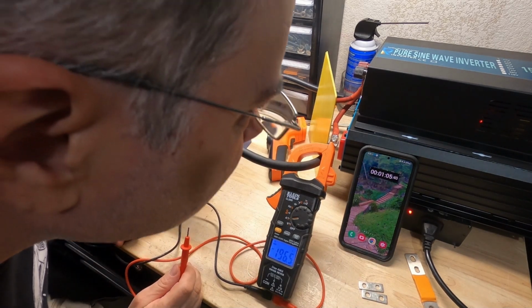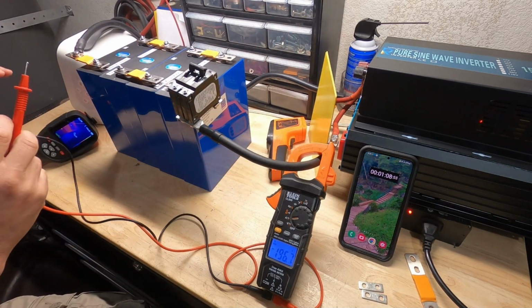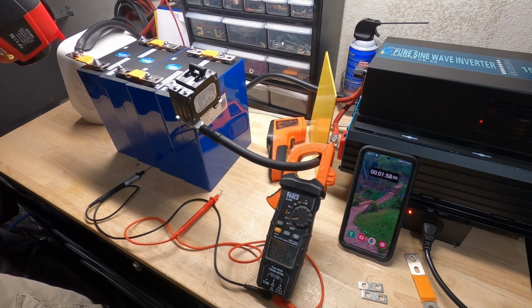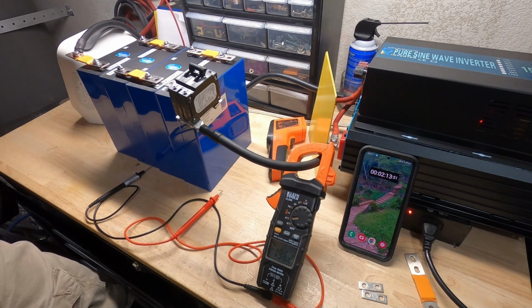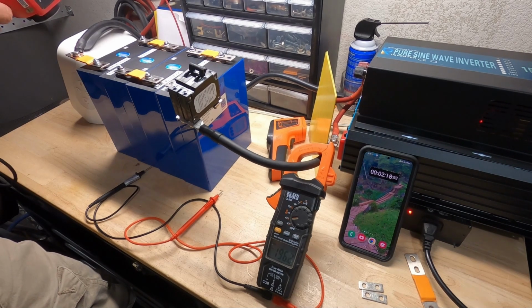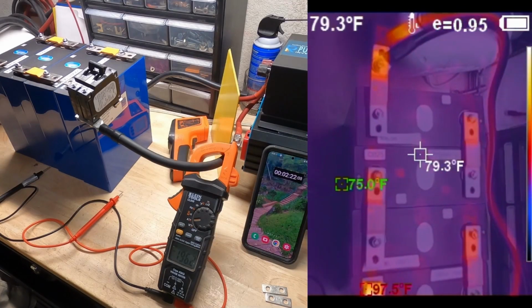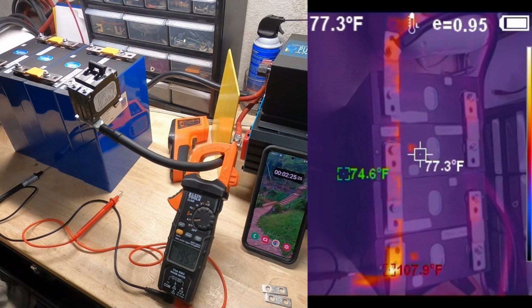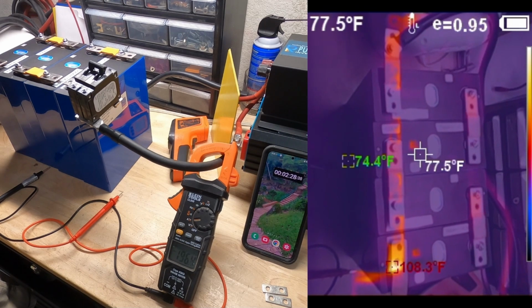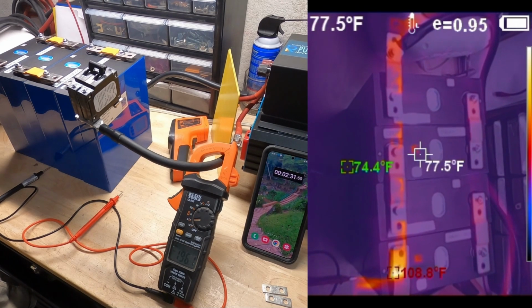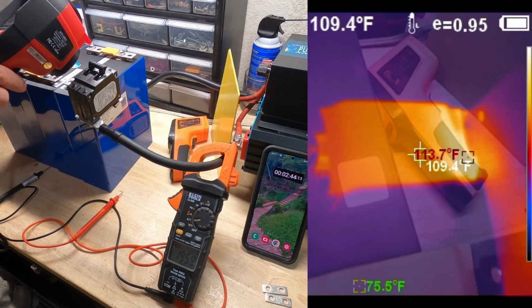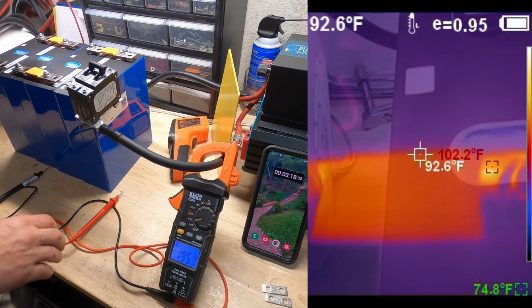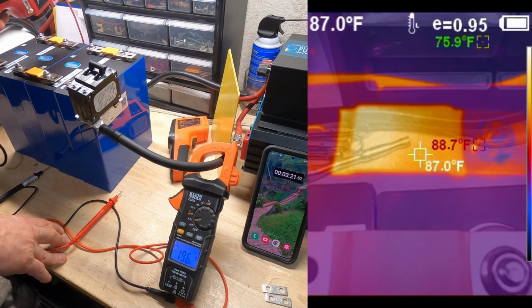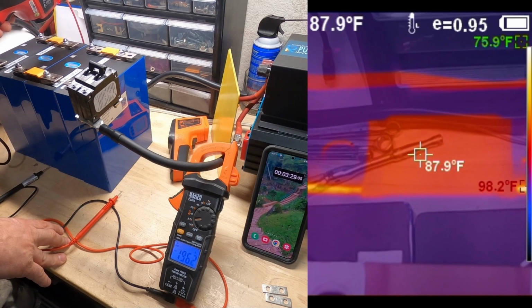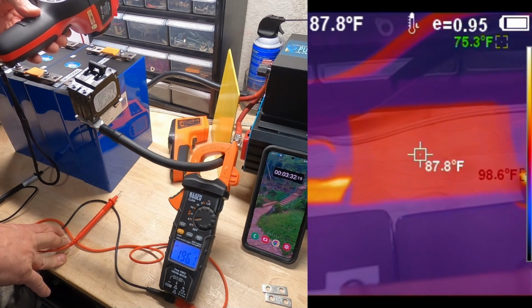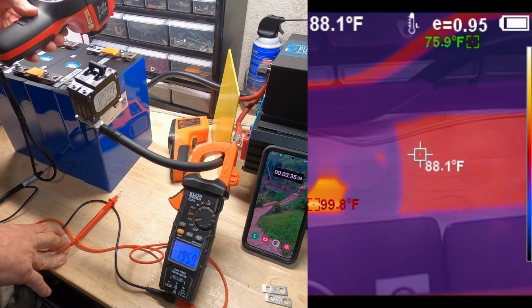Right, what the hell is that buzzing? The inverter? Jesus. Okay, we're coming up on 2 minutes. We're gonna do our check here. I'm doing the overlay mode so we can kind of see what we're looking at. So I'll just do an overview here. Looks like the bus bar on the breaker is the hottest. 113. About 102 there. 102 on that one. That one's surprisingly cool. About 100 degrees though. Same with that one, about 100 degrees.